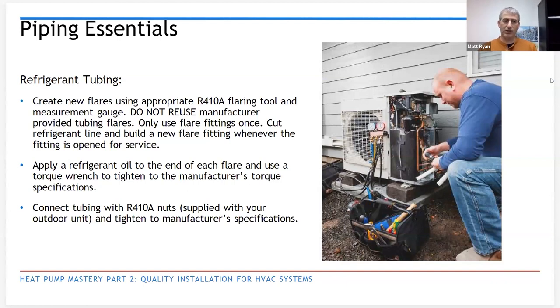It's changed so much. We use that Nylog just as a secondary helper there, and then using the supplied flare nuts. There are not as many, but there's still some stuff out there for oil pipe, oil furnaces. That flare is different than what we use for 410A. It's not as much as a handful of years ago, but that was a thing to really watch out for. Still is, just not as much.